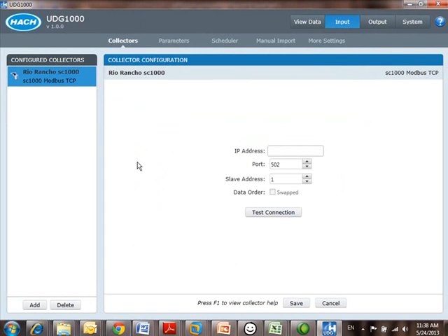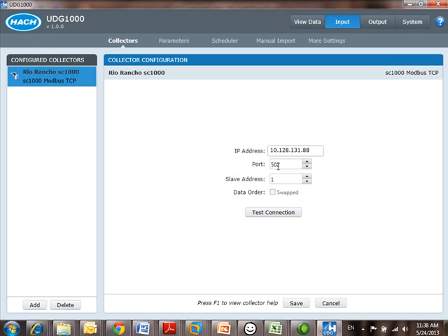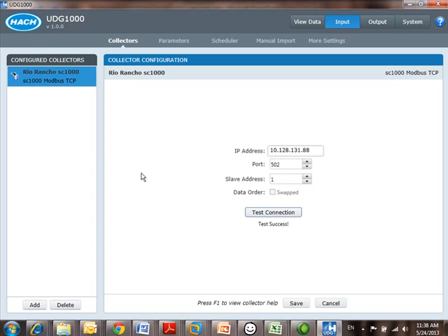How do we communicate to it? In this case, I need to type in the IP address, so that's 10.128.131.88. I specify the port and slave address. Those are defaulted in this case. They're correct, so I click Test Connection, and the system goes out, pings that IP address, makes sure it's an SC1000, so we're communicating, and I'm going to go ahead and click Save here.